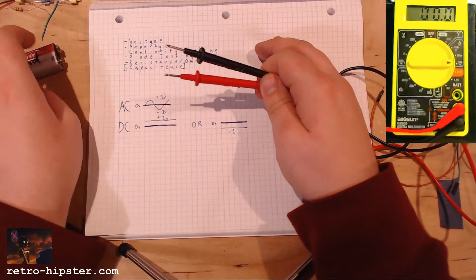I've got my meter in DC amperage mode at 200 milliamps. Since I'm doing a low power circuit, I'll use the low power socket - notice there's a separate 10 amp socket we're not touching for now. This supports up to 200 milliamps. I'm going to bring in my meter to my test circuit. I don't know how much power this is using yet, so like with voltage, I'll shoot high - I think it's less than 200 milliamps, but I don't know how much less. It could be in microamps, could be whatever.